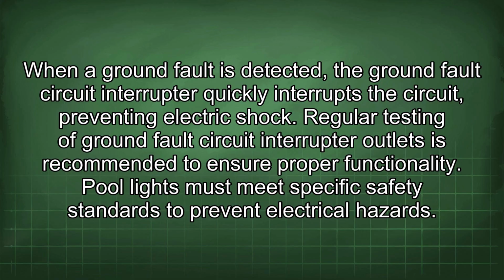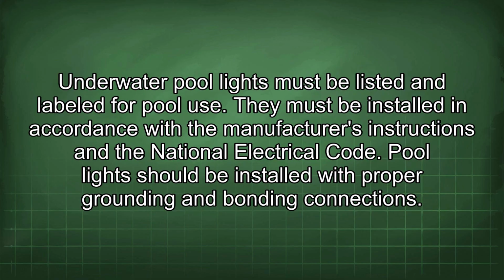Pool lights must meet specific safety standards to prevent electrical hazards. Underwater pool lights must be listed and labeled for pool use. They must be installed in accordance with the manufacturer's instructions and the National Electrical Code. Pool lights should be installed with proper grounding and bonding connections.